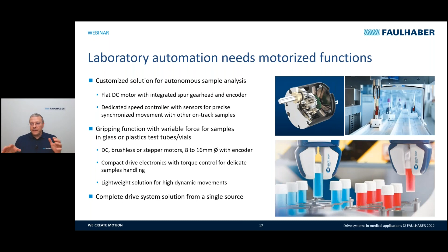Automatic analysis machines like this one need high speed and high precision. We have standard analysis protocols, and for example, the multi-sample plate, like in this case here, has a very small raster, below 10 millimeters. For this reason, it's necessary to use DC and brushless micromotors with diameters of 6, 8, and 10 millimeters.